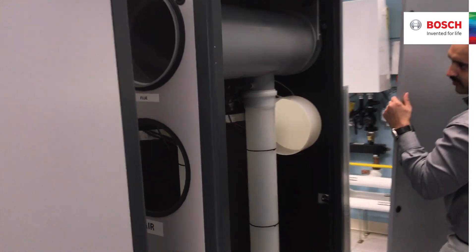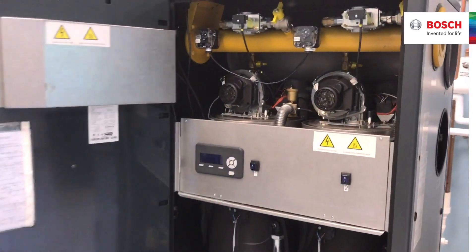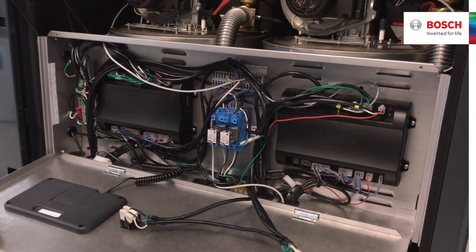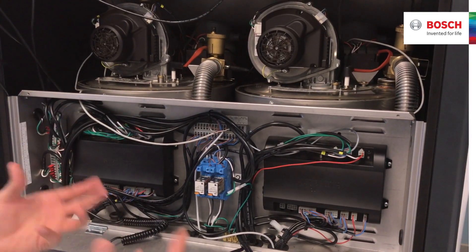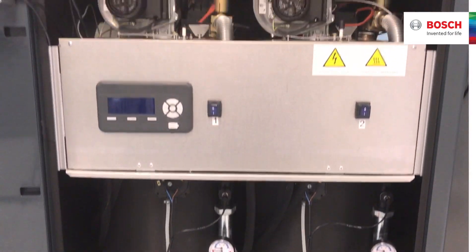The larger series models have removable panels, allowing easy access to all internal areas of the boiler. The cabinet includes two heat engines to allow serviceability of one while the other continues to support the system. Both have dedicated controls, primary pumps, check valves, and isolation valves.